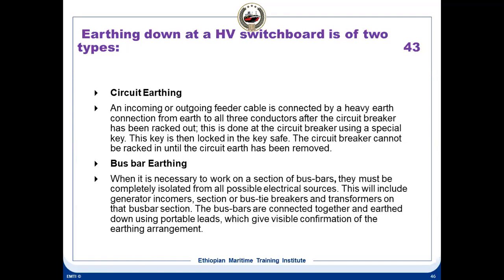The circuit breaker cannot be racked in until the circuit earth has been removed. In this case, when you rack out the breaker, at the bottom of the breaker there is a key slot. You have to put a handle there and push the handle down. That will make an automatic grounding there. This is called your circuit is totally earthed. That means from the generator to the breaker is grounded.